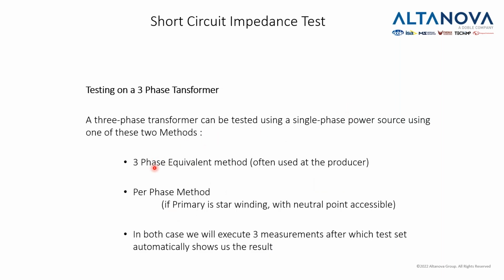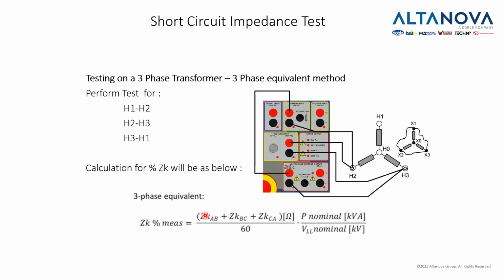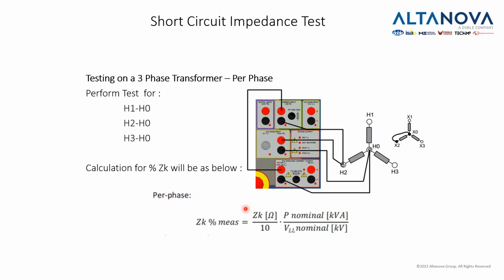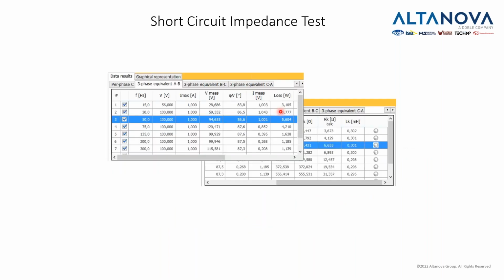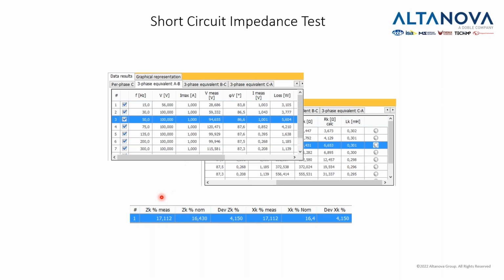And we have 2 methods, 3-phase equivalent and per phase method. We usually use 3-phase equivalent because per phase method is applicable only if we have a star winding with neutral point accessible. In both cases, we do 3 measurements. So this is the example for a 3-phase transformer, 3-phase equivalent method. And this is the formula which we would use to calculate Z percentage. This would be the connection for per phase method. And as we do the test, we get 3 results. And here we see the measured and the nominal value.